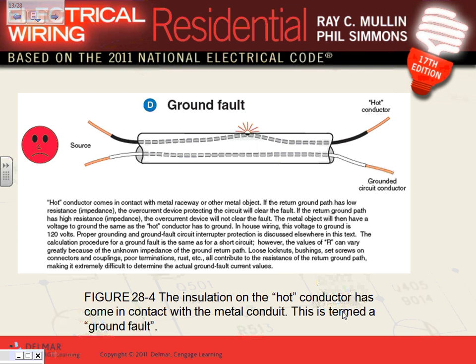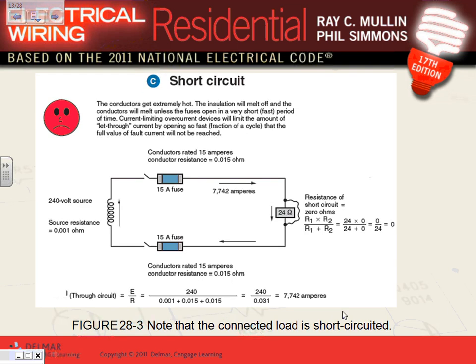Any question, my friends? So ground fault, what's the difference between phase? Lower amps. As you guys can see, we got 4K here versus we got 7.7. How did you get the 4K? Not rocket science. You take the 240 volt, take one impedance here, the other impedance, the impedance of the grounded conductor too, and the impedance of the connection here, that connection that has an impedance. It might not be touching. You know, there is a gap, a little gap, or something starts arcing. So they all take this into consideration. Almost always guaranteed you're going to get lower than that.